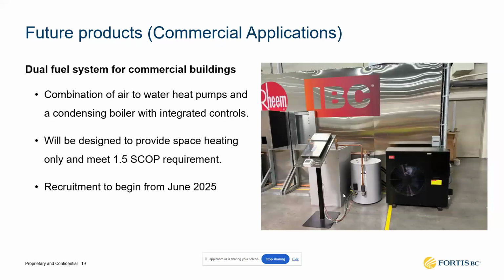Now switching back to commercial, this is another pilot we are working on. This is a dual fuel system for a multi-unit residential building, and this consists of an air-to-water heat pump and a condensing boiler, working with integrated controls. We're still working on different configurations, different brands. The one that I'm showing here is from IBC, but we will work with whatever product we find suitable for our pilot.